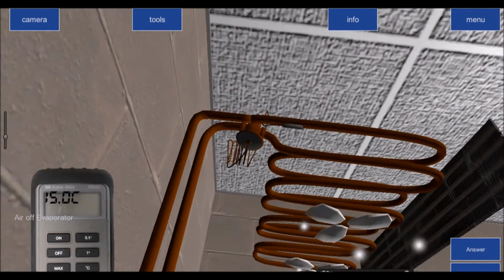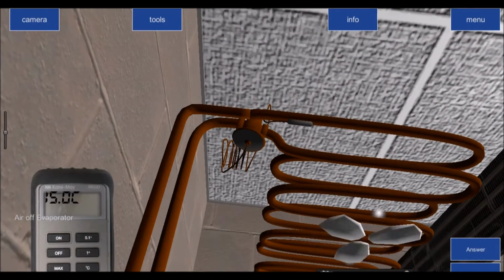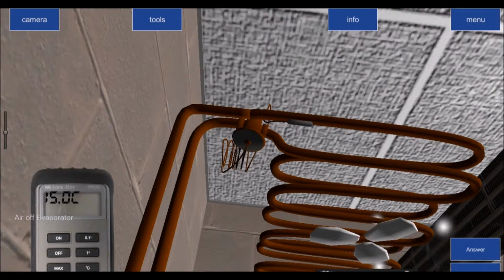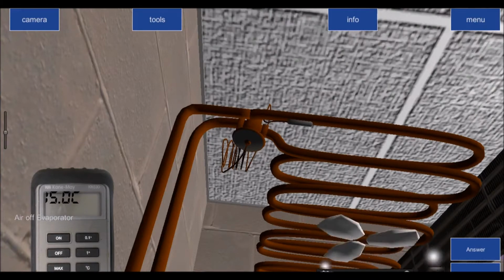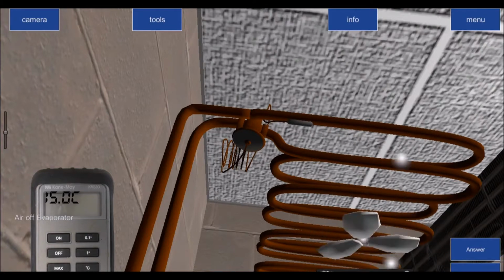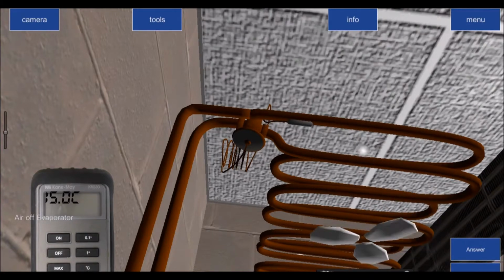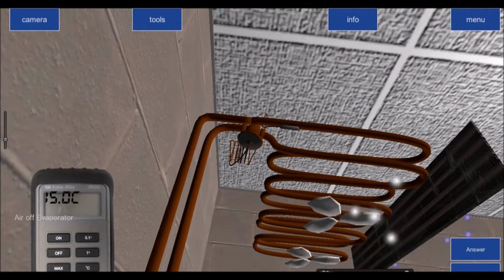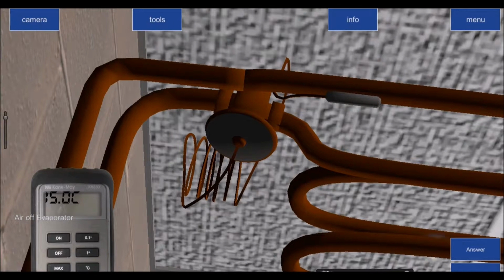Right, now, with my thermometer, the main difference between this setup and the setup you have in the previous menu, which was the workshop setup, is that the thermostatic expansion valve on this one is in the correct place. It's at the inlet to the evaporator. It's not out on the bench like we had earlier on. So if I put my thermometer anywhere between the outlet of the thermostatic expansion valve and the inlet of the evaporator, where the bulb is clamped is representing the outlet. If I put my thermometer there, you can see it says the end of the evaporator coil, so that's representing the outlet of the evaporator. That's your suction pipe going back to the compressor.